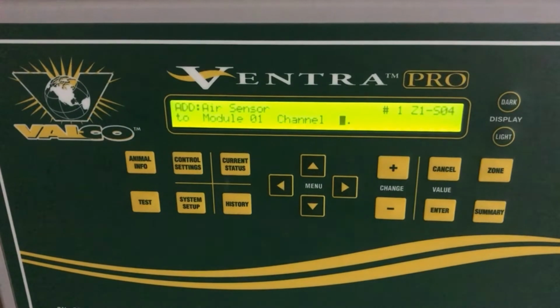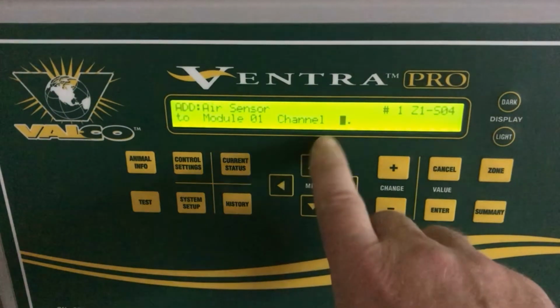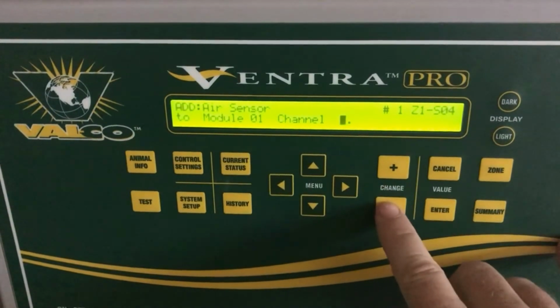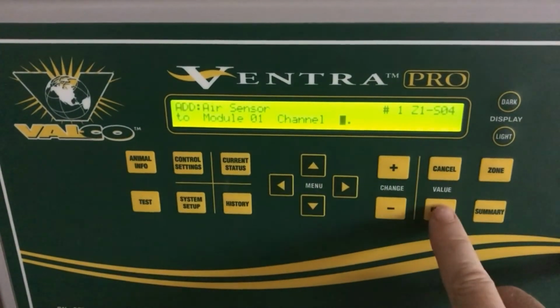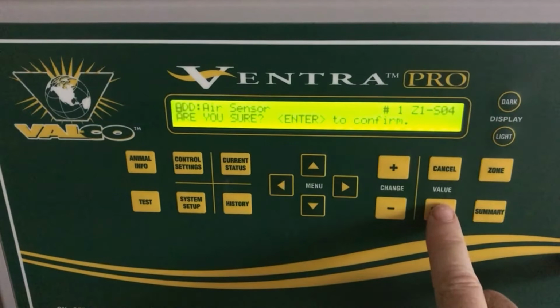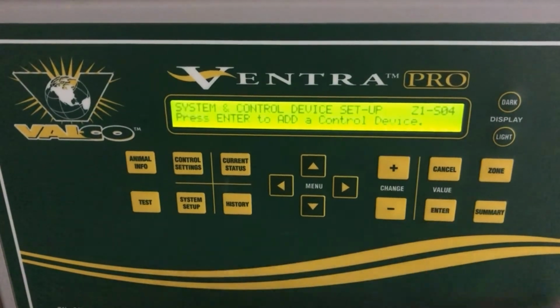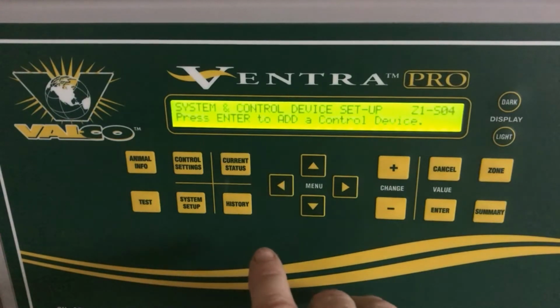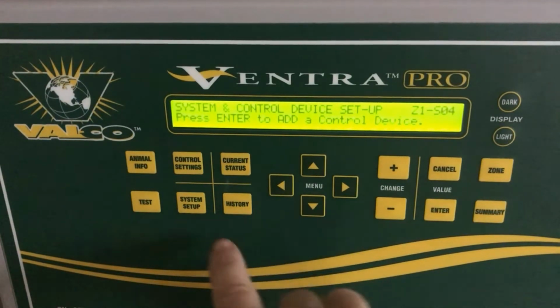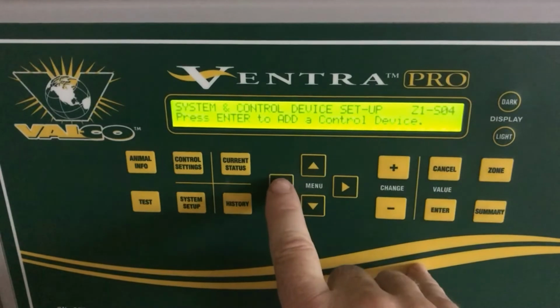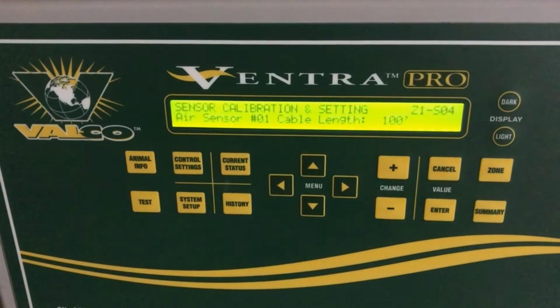Press Enter, and now you choose the channel on the input analog board that the sensor is wired to. In this case, it is wired to channel 7, so I will leave it on channel 7, press Enter, then press Enter to confirm. Now I have added the temperature sensor. To complete setting up your temperature sensor, from the System Setup, you menu arrow to the left once, and then you will set up your sensor calibration and settings.